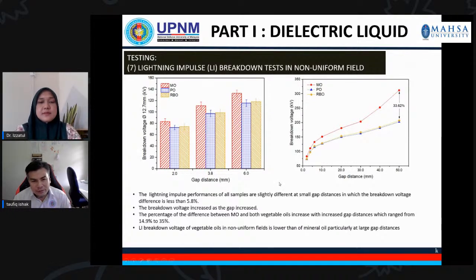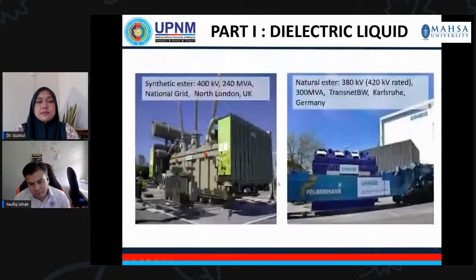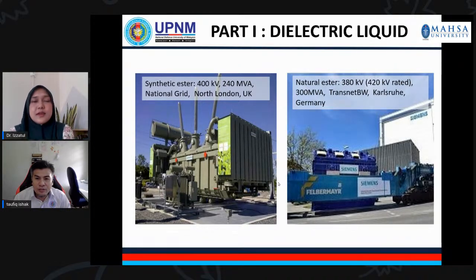Right, that's all the results that we have for the liquid insulation. And these are real transformers that use synthetic ester and natural ester. One is in the UK, using synthetic ester in a 400 kV 240 MVA transformer located in North London. Then we have another one using soybean oil in Germany, in a 300 kV 300 MVA transformer. So different kinds of oil have been used inside transformers.